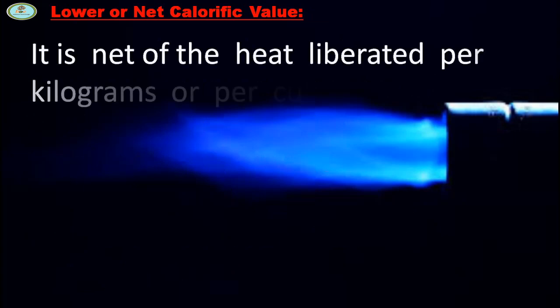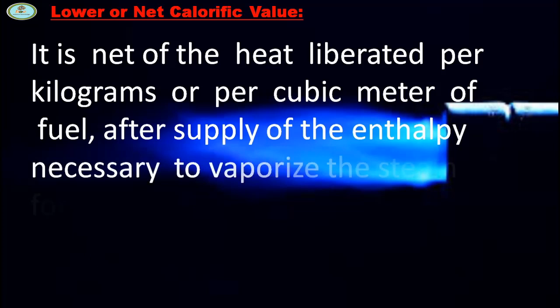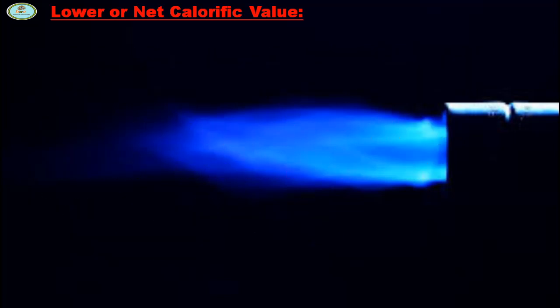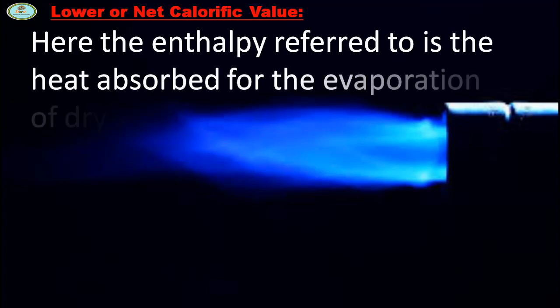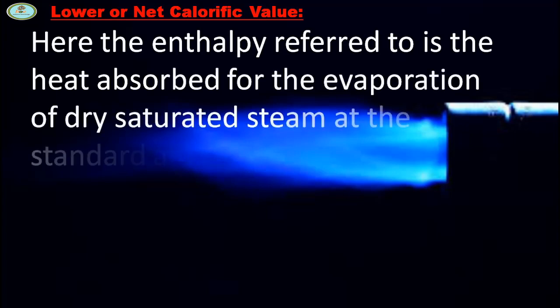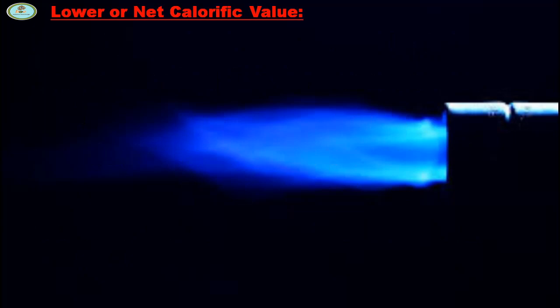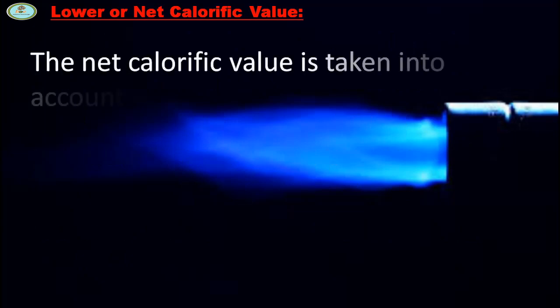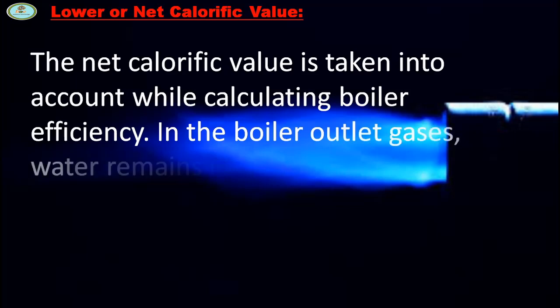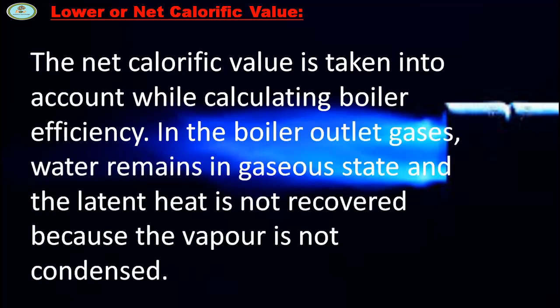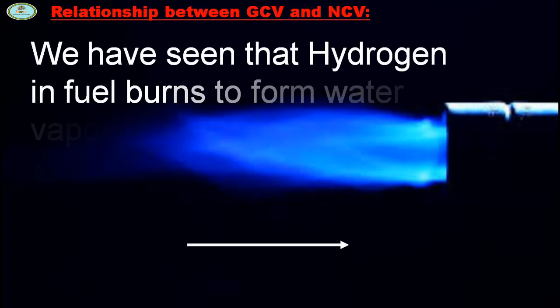Low or Net Calorific Value (NCV): it is the net heat liberated per kg or per cubic meter of fuel after supplying the enthalpy necessary to vaporize the steam formed by combustion of hydrogen in the fuel. The enthalpy referred to is the heat absorbed for the evaporation of dry saturated steam at standard atmospheric pressure of 760 mm of Hg. It is the gross calorific value minus the heat loss due to hydrogen. The net calorific value is taken into account while calculating boiler efficiency, as in the boiler outlet gases, water remains in gaseous state and latent heat is not recovered.